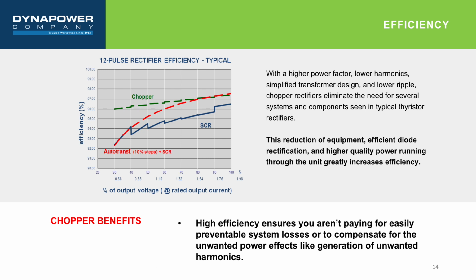Efficiency. Compared at maximum rated output, the 2 types of rectifying equipment, thyristor and chopper power supplies, generate similar losses. However, the difference between the 2 topologies is significant at lower output power requirements. The chopper transformer losses are lower than the thyristor transformer losses due to the simplicity of the design and the significant absence of harmonic currents. The transformer primary currents are similar in both chopper and thyristor power supplies at maximum power factor and full output power. As soon as the thyristors are phased back because the line voltage is higher or the output demand is set lower, the transformer primary losses are higher due to the poor power factor and increased harmonic content. Additional losses in thyristor rectifier systems are generated in harmonic filtering equipment, which chopper rectifiers do not require. High efficiency means we are not paying for easily preventable system losses or to compensate for unwanted power effects like harmonics, thus the advantage of the use of chopper rectifiers.